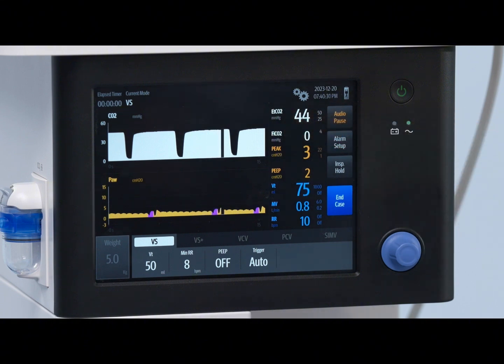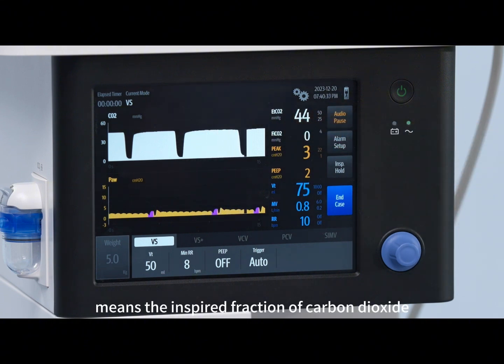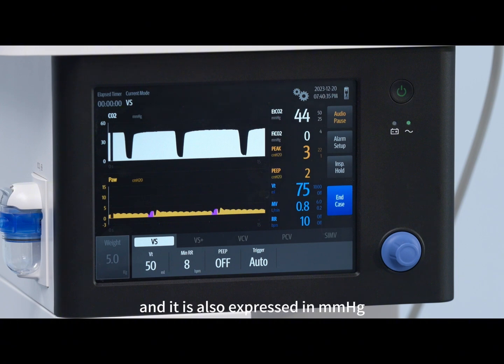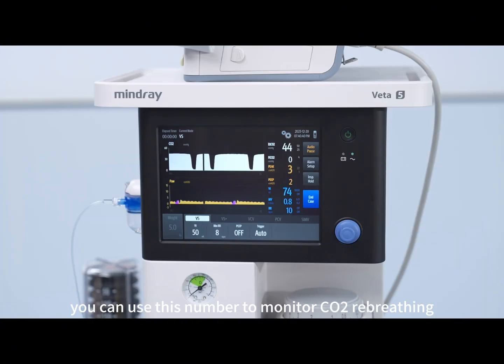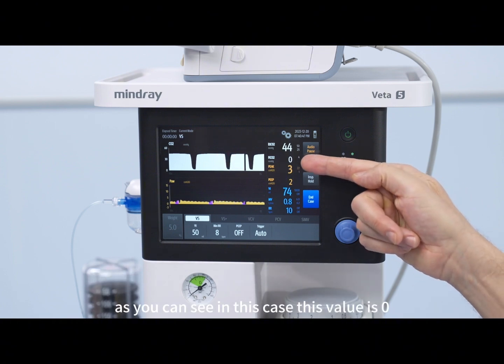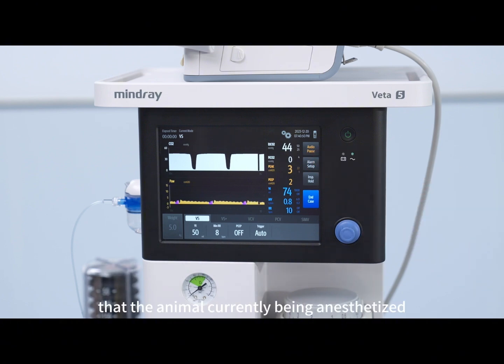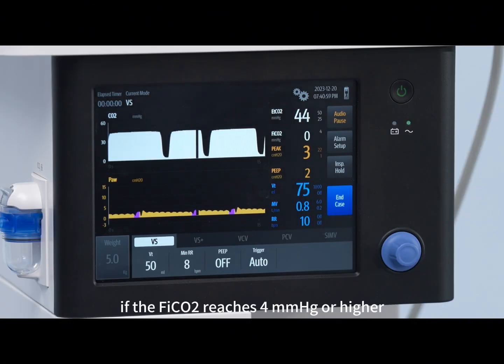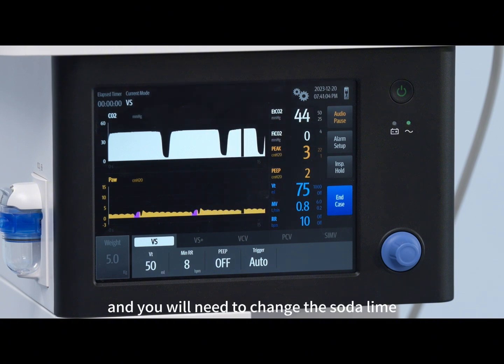FiCO2 here means the inspired fraction of carbon dioxide, and it is also expressed in millimeters of mercury. You can use this number to monitor CO2 rebreathing. As you can see, in this case, this value is 0, which means that the animal currently being anesthetized, which is a small dog with 5 kg body weight, is not rebreathing CO2.